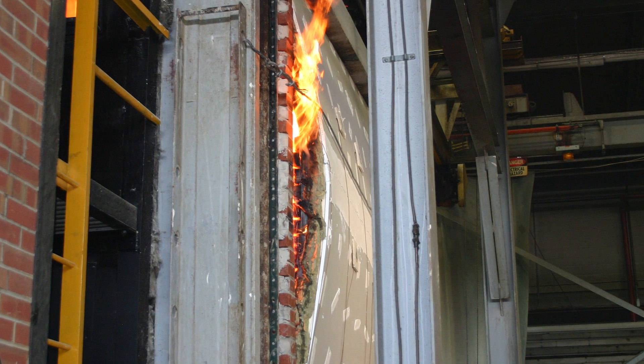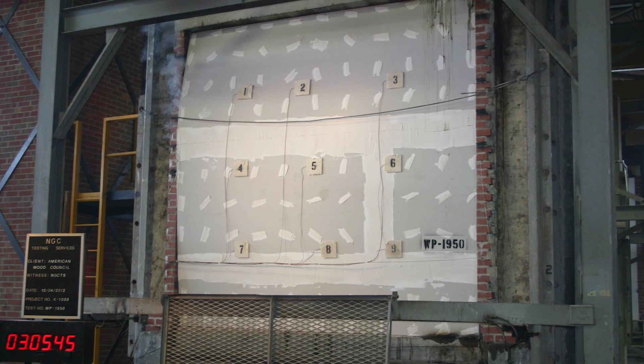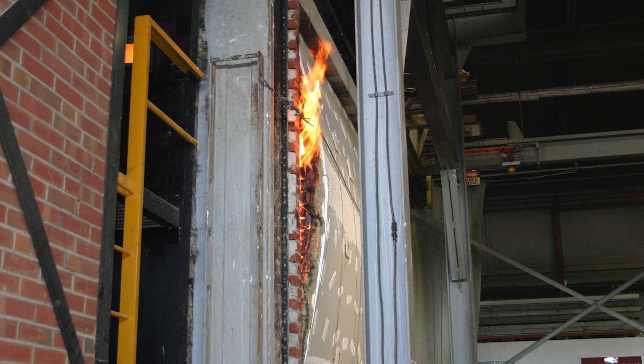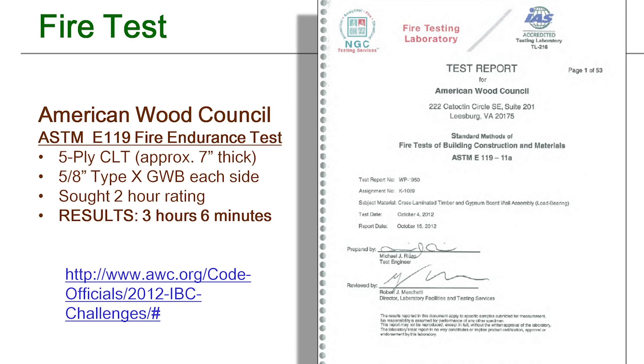Within Type 3 construction, there's a requirement for a fire resistance rating. Under the current code, there are no fire resistance provisions for cross-laminated timber. To meet those provisions, one option is the calculated method. You can also utilize testing done by the American Wood Council, which showed that an assembly of 5 plies of cross-laminated timber with 5/8-inch gypsum on each side can last beyond the 2-hour resistance rating — up to 3 hours and 6 minutes. The fire test performed was ASTM E-119, which is a requirement within the code.